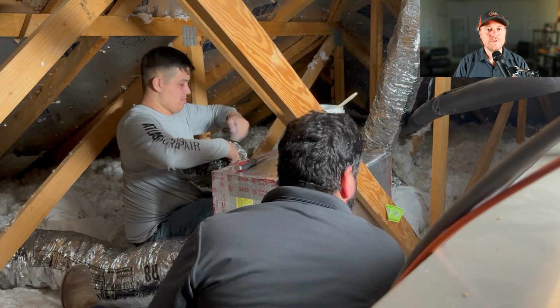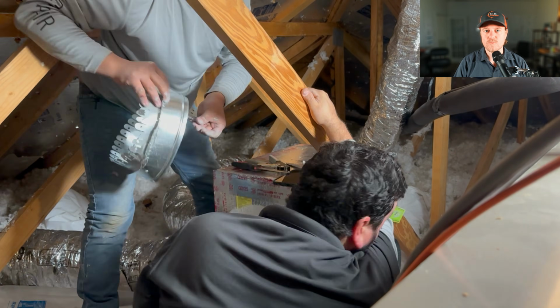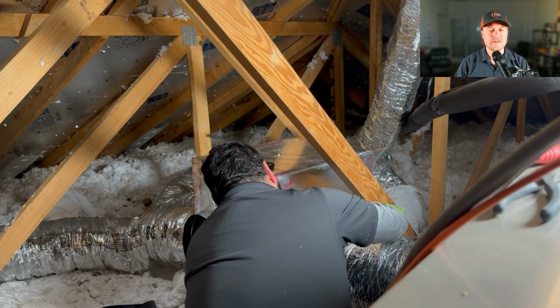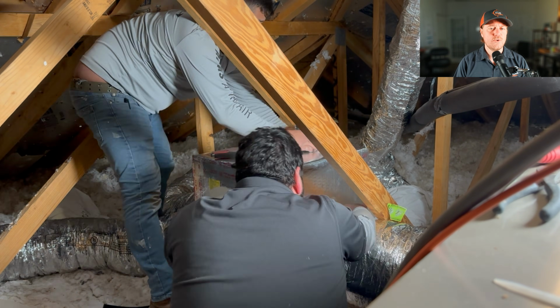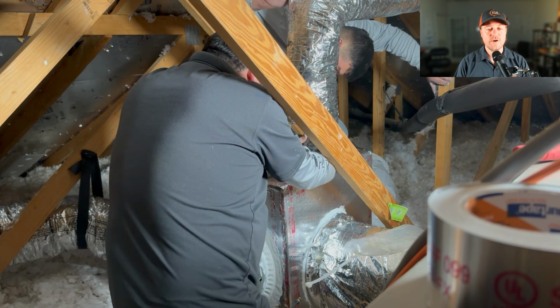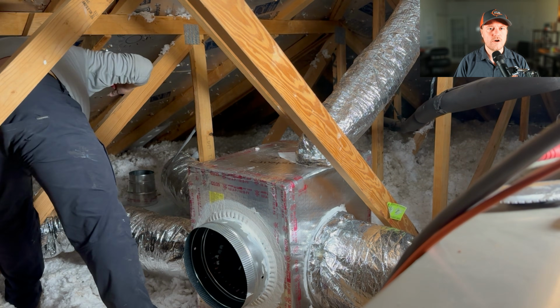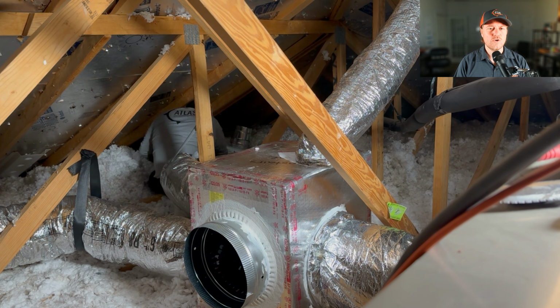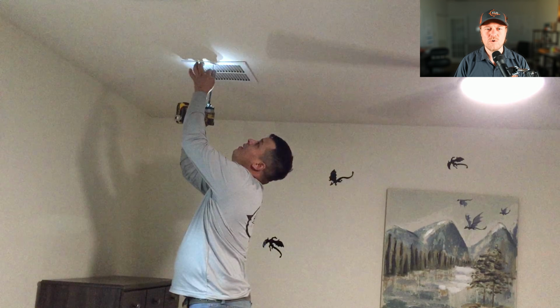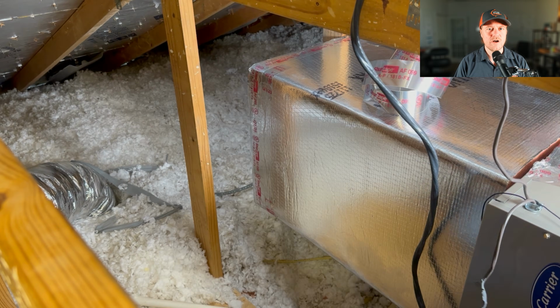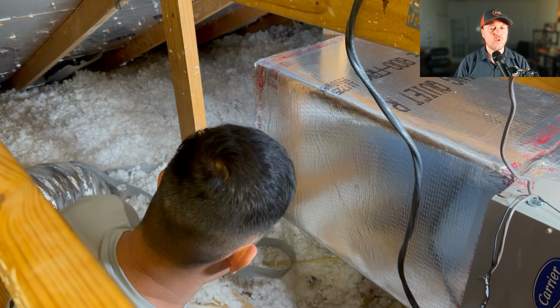Now that we got all the old ductwork out of the way, we now have some working room. Alright, let me give you all a quick rundown on the next steps. Now at the open space, we can put in the distribution boxes that we built the day before. From there, we're going to run our flex ductwork. Then where needed, we're going to put in new register boxes. Then we'll attach the flex ducts to the register boxes, along with putting in our supply or return grills.